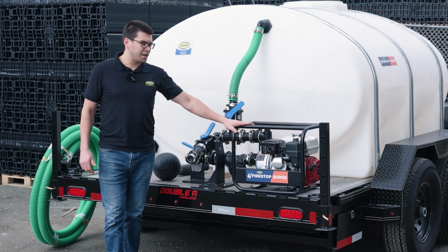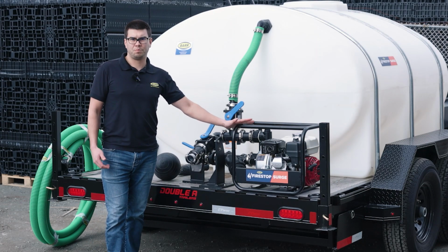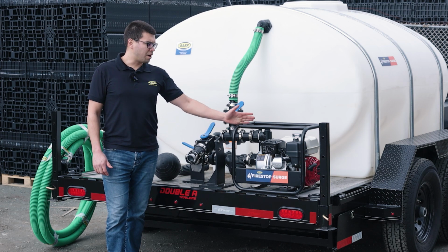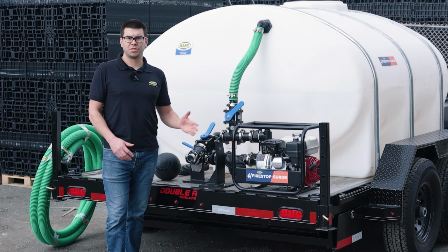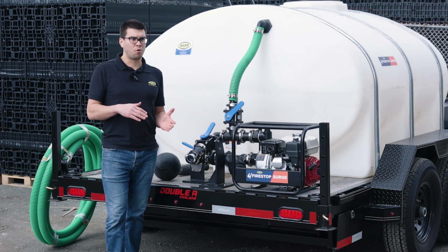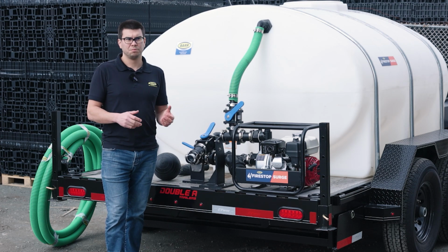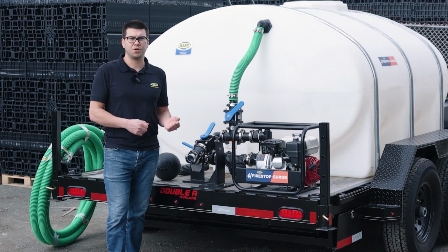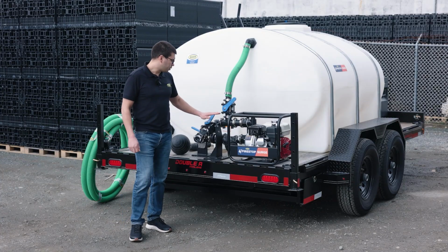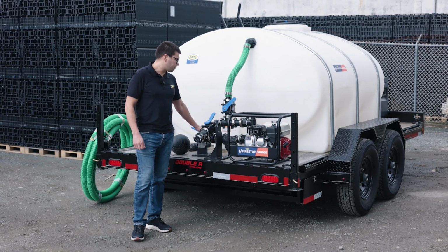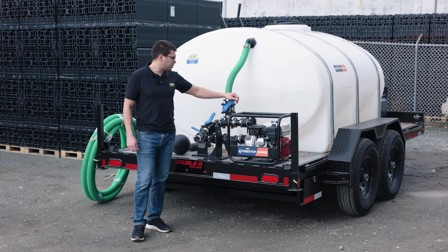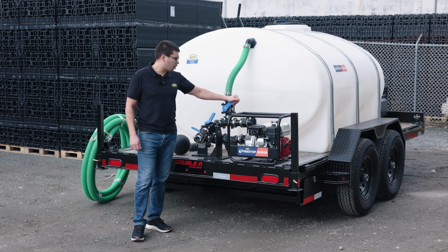You're going to use the 85 PSI pump, which will be able to shoot about 80 feet of distance for the water through a 50-foot fire hose line. The longer the hose you use, the more resistance there will be, so your discharge distance will decrease a little bit.